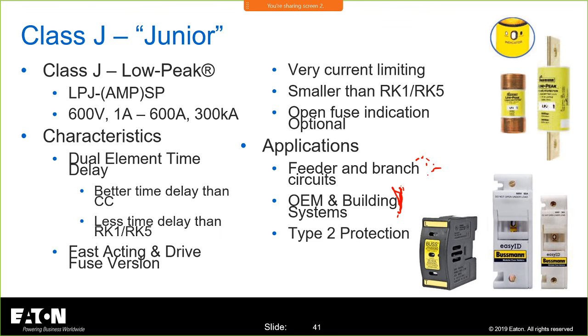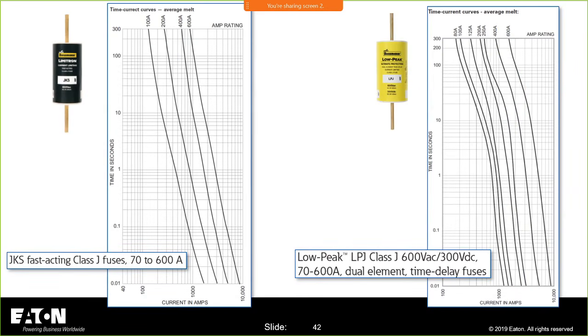OEMs and building systems. Type 2, I didn't put any slides in here on type 2 protection. That is basically that once these things open, if they open, you have much less damage inside of that enclosure because they go so fast. Look at the curves. You'll notice the difference between the fast acting, look at that slope. Look, this is your dual element time delay. You've got a hump in here. You don't have that over here, right?